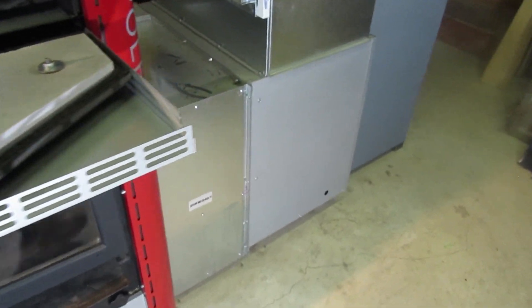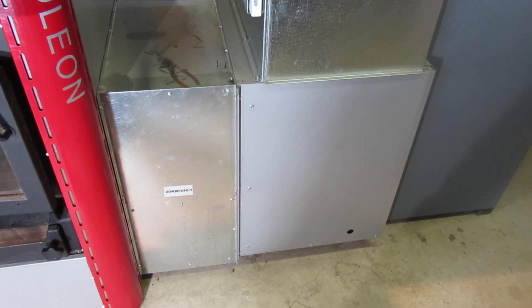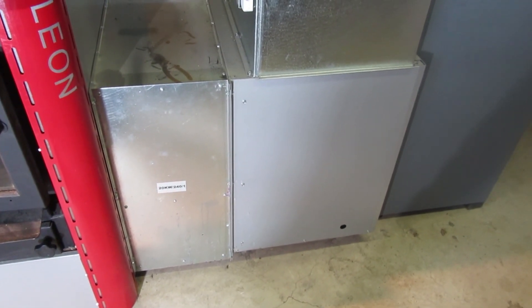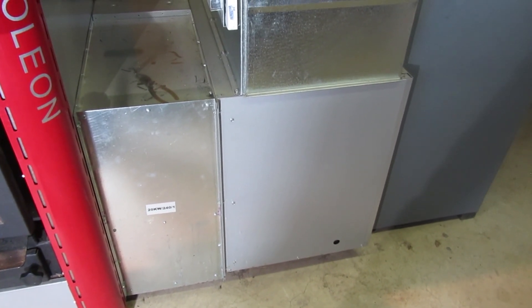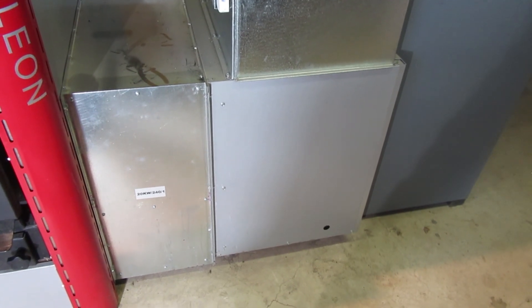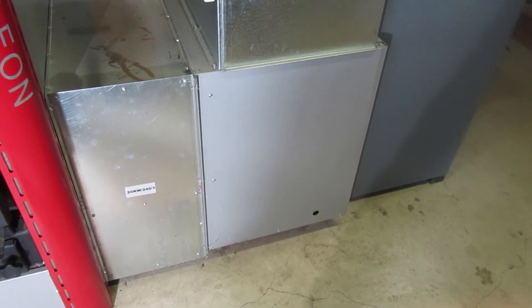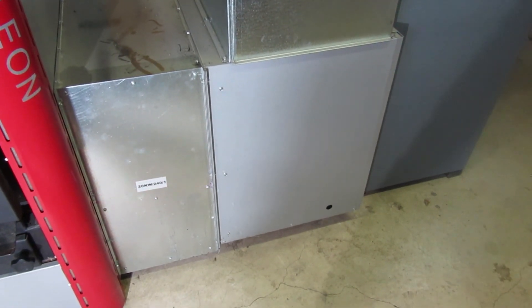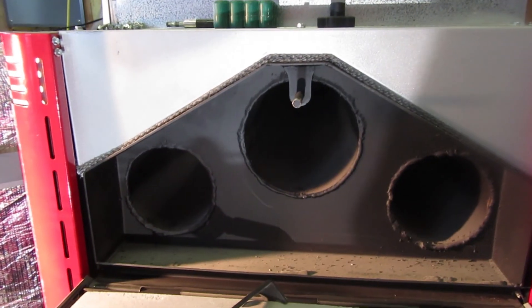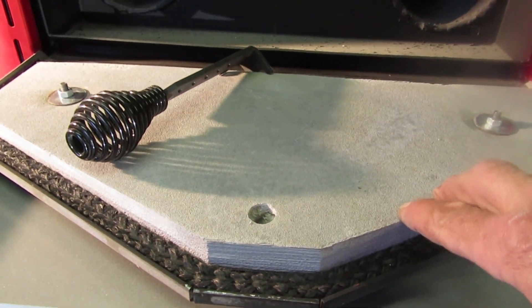The blower is optional and sold separately. If you do go with the gas unit, I'd recommend bypassing this blower and going with an ECM blower instead of the three or four speed blower. An ECM is a continuously and infinitely variable speed blower — all high-efficiency furnaces use them these days. They use a lot less power and are computer-controlled based on CFM, moving exactly the amount of air the computer tells it to. They're way more efficient.